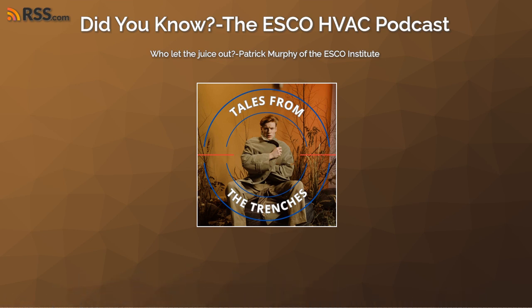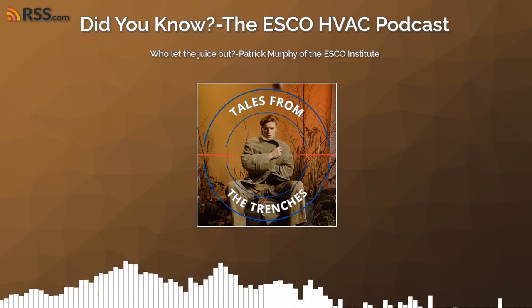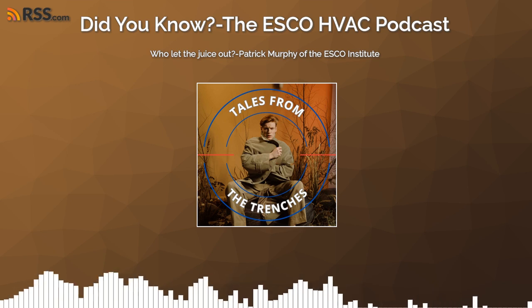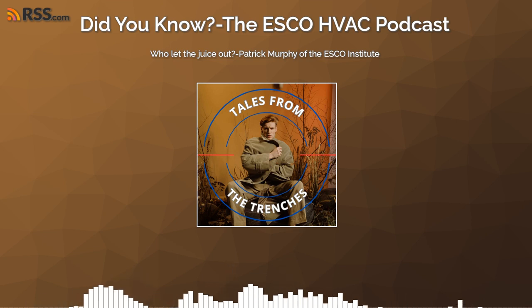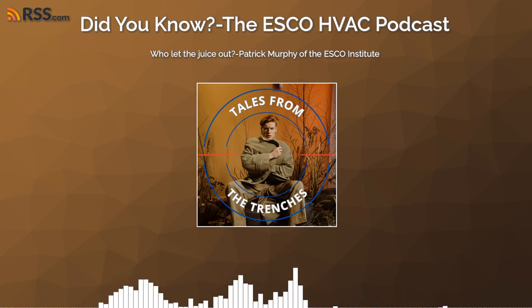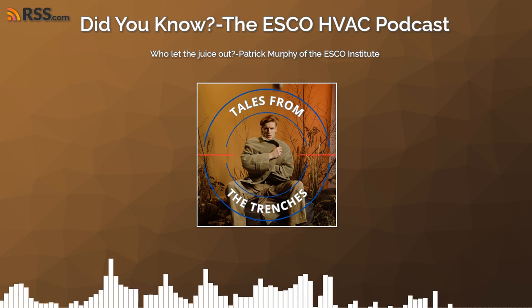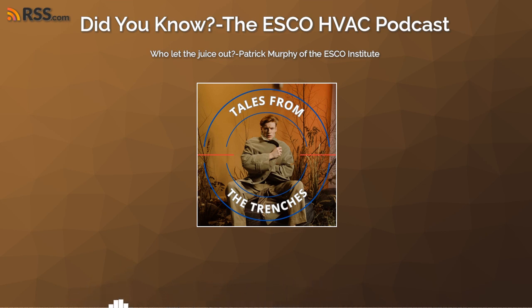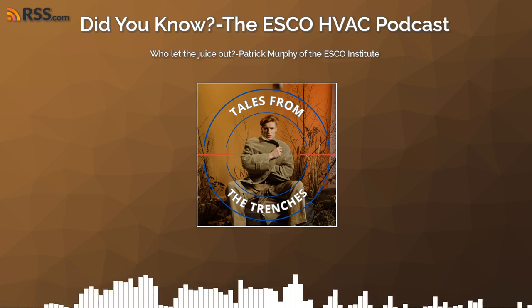Now, if you have a brand new system that you've just installed and you've got a leak, you're going to be tearing your hair out. That's exactly the circumstance we ran into. We had a brand new system installed in a supermarket — it ran three meat cases. The machine room was downstairs in a basement, and we charged the whole system up. It was running fine for two or three days, and then it started to leak. We were in the cases, in the machine room, shutting things down and building pressure up to 400 PSI — the maximum those evaporators could handle — and we could not find the leak.